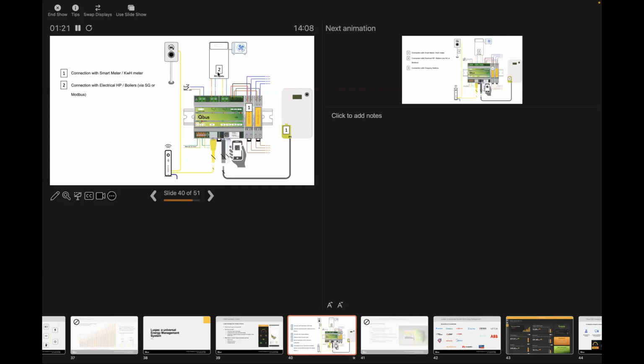Two ways of connection are possible, or smart grid ready. Most of the new heat pumps coming out have this interface called SG, smart grid. It's just two contacts, very simple, but it's a standard among heat pump manufacturers that they provide these smart grid contacts on each of the heat pumps. With the two contacts you can basically control four modes: normal, off, boost, and economy. That's basically how you communicate.